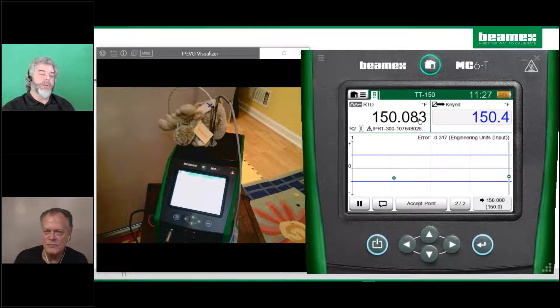Now it wants us to manually enter the full scale. So I'm going to call the control room and key in 150.4. Let's see how that looks. Oop, it's failing, but this temperature dropped. So this is a little quirk in our dry block. It shouldn't stop controlling. But if this were real, we would sit here and wait for it to become stable again. It's only that we're doing a live webinar that we're trying to hurry things along. So it's not fair.